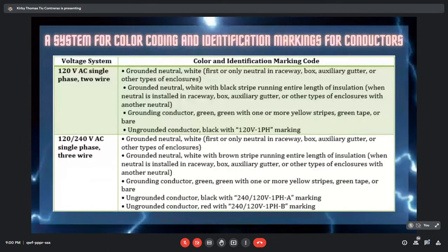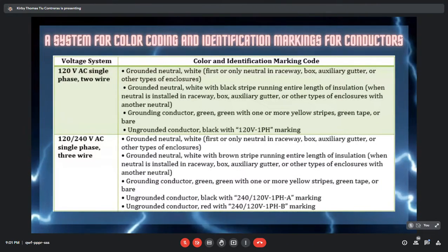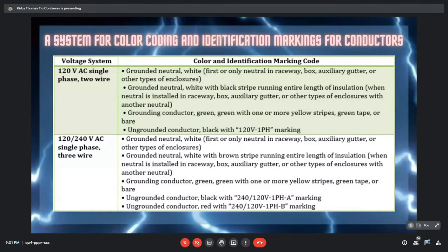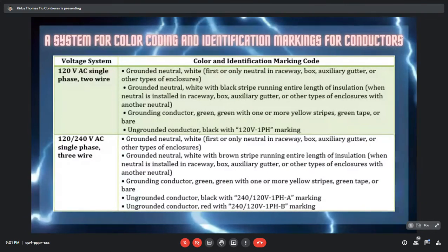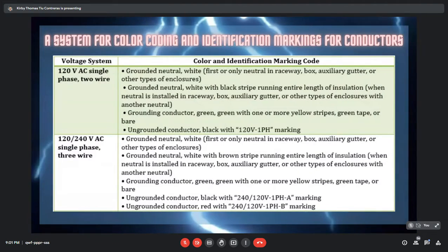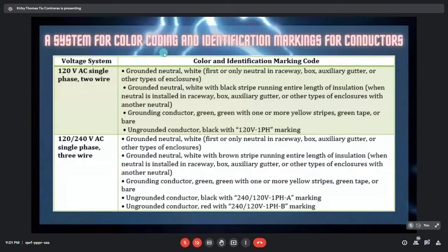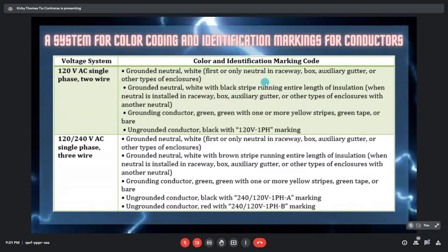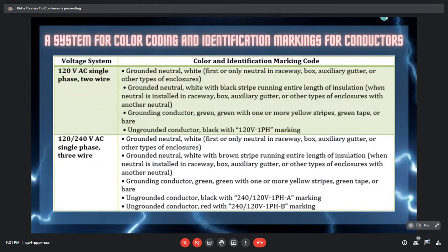For example, in this table, for 120 volts AC single phase 2 wire, the color identification for the grounded neutral conductor is white, or white with a black stripe running the entire length of the insulation. An example of an identification marking for the ungrounded conductor is a color code of black with a marking of 120 volts single phase.